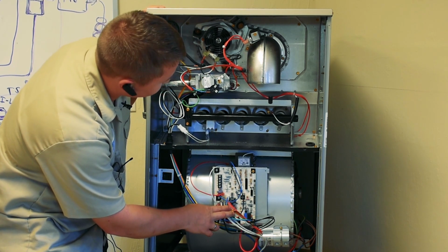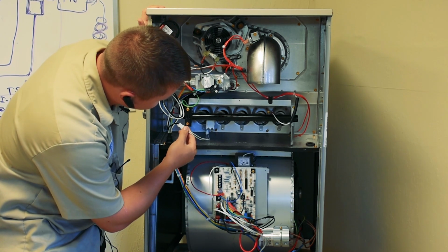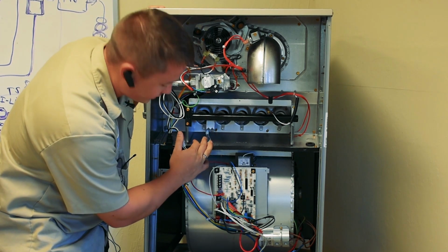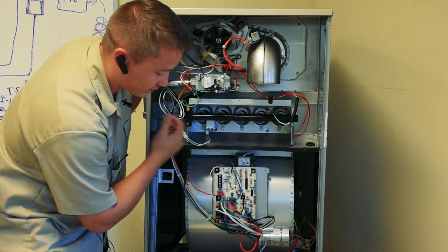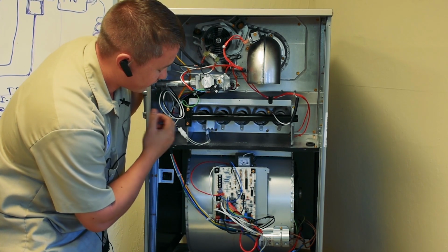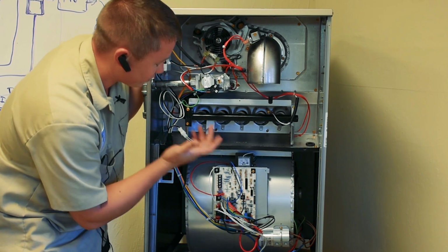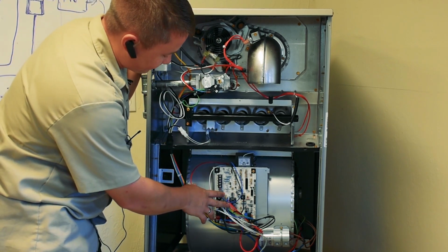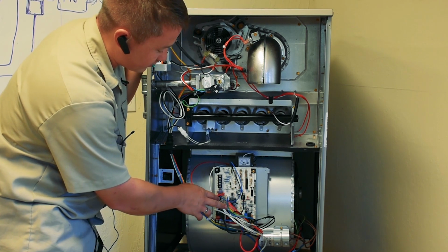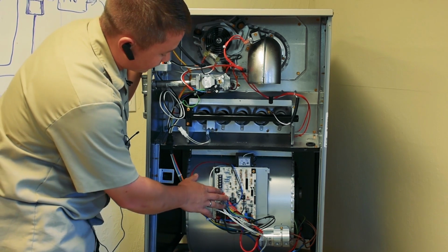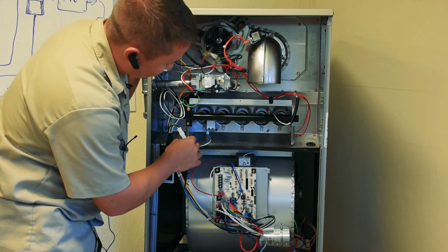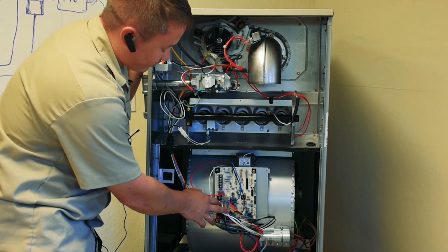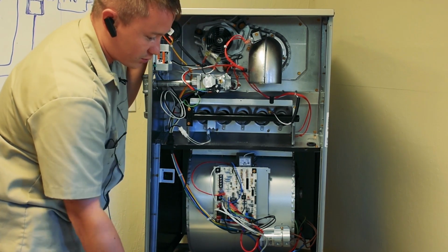The next relay will send the 120 volts power to the igniter. The igniter will ignite, getting a red or yellow color, and you will see that. Then the control board, depending on the model, could sense the change of resistance of this igniter, or will just run the igniter by time, like 10 to 30 seconds.